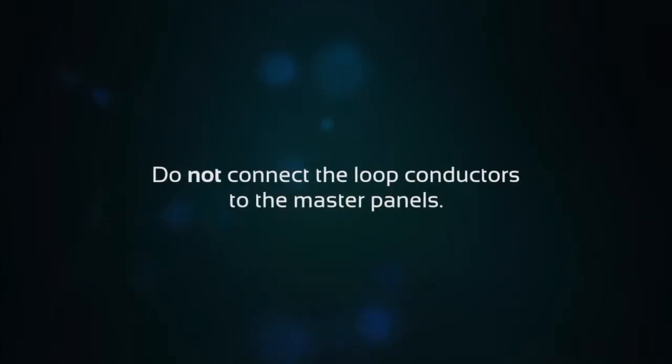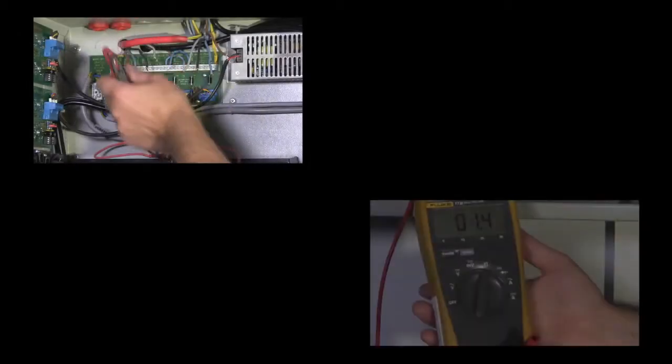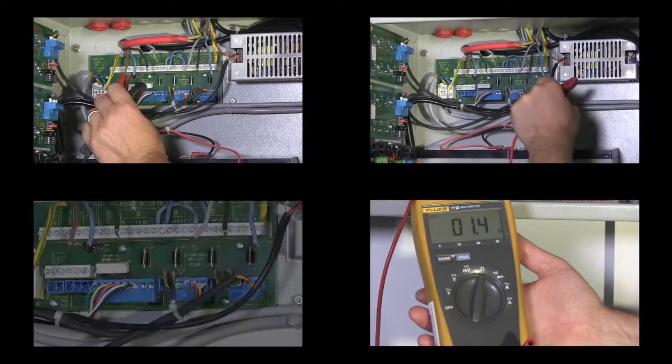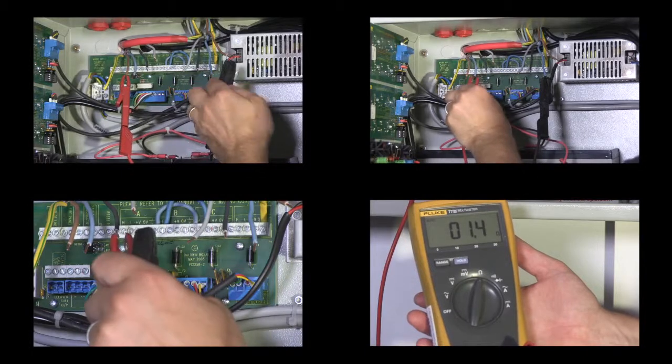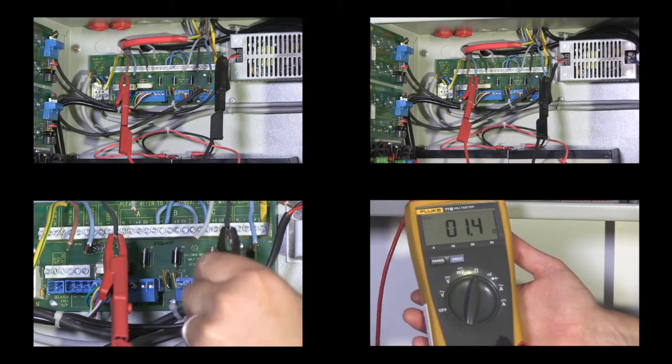Do not connect the loop conductors to the master panels. It is necessary to leave these as trailing ends. Now check each loop conductor with a multimeter to ensure there is full continuity and no shorts to earth or to any other conductors.